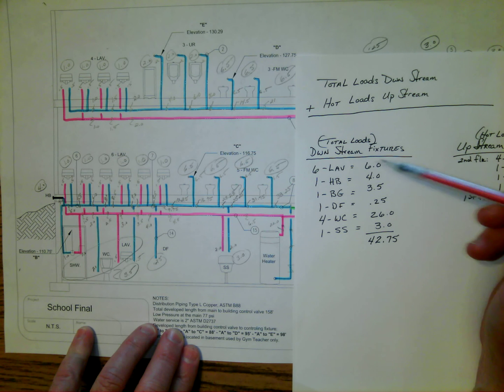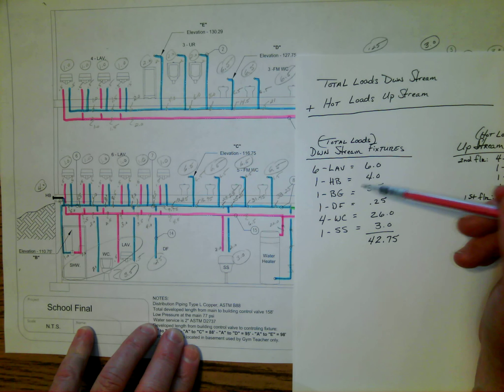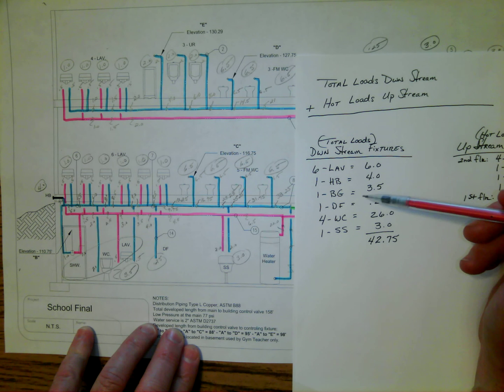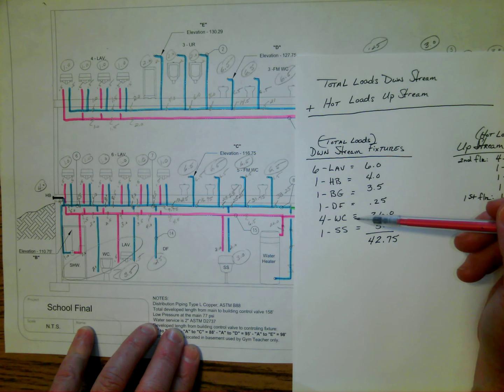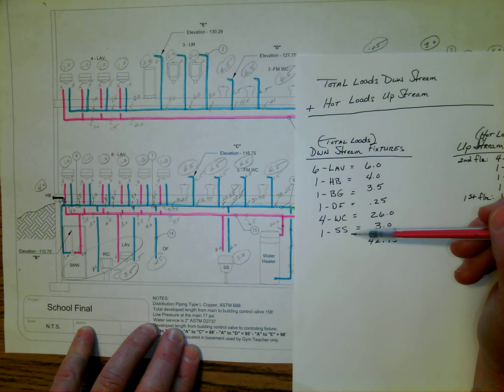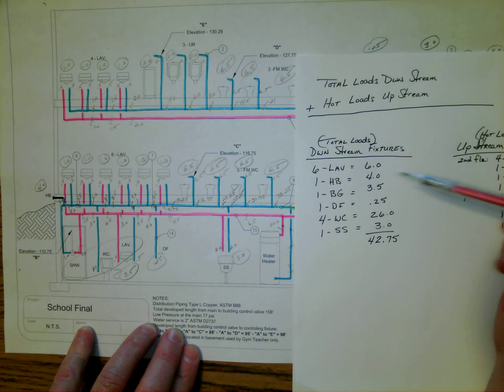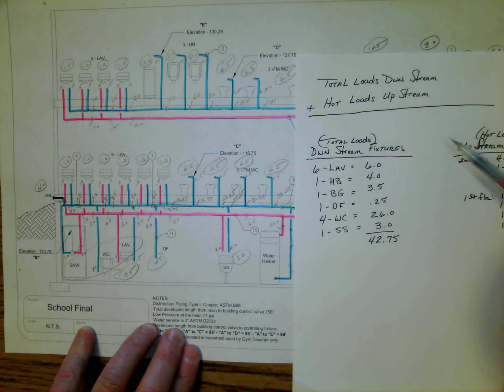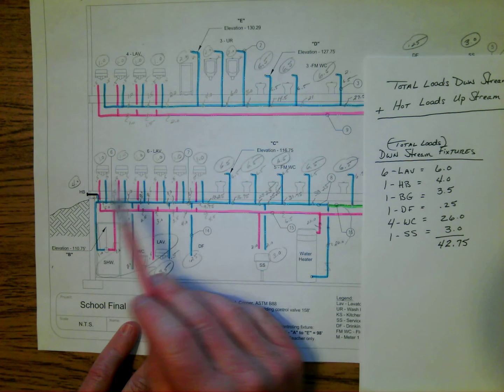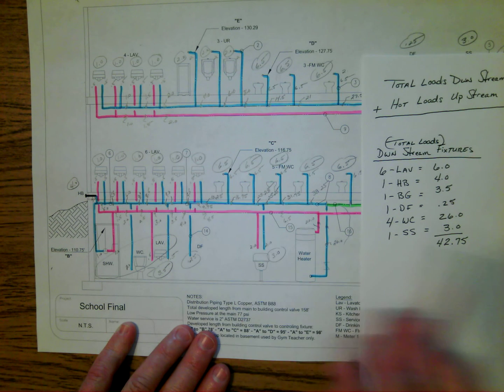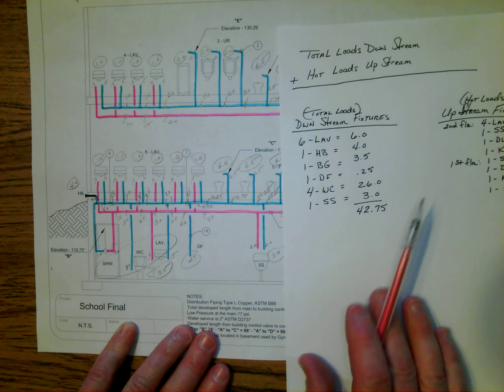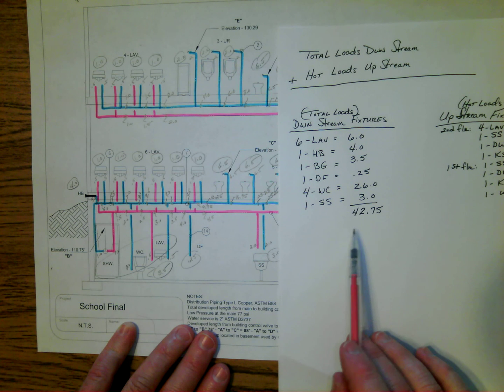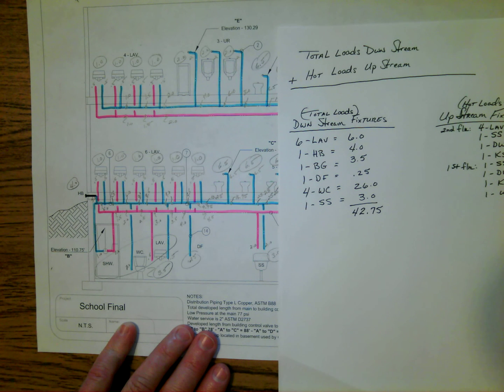So we had six lavs for a total of six WSFU. We had the hose bib, which was three-quarter inch. We had a bathroom group. We had the drinking fountain, and we had four water closets and a service sink. So with all of these fixtures, I took a look at all of the total loads. I added them up, and at this point, the total load downstream is 42.75.